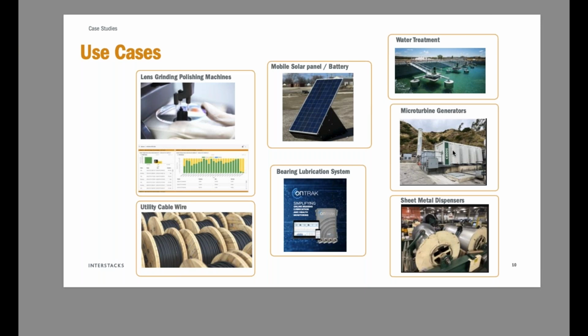We capture data from turbines and generators and send it to the visualization database. This company, Bearing Lubrication System, is an OEM that makes ultrasonic sensors for bearing wear and lubricating bearings, which is a big failure mode. We capture data from their sensors, package it up, and put it on dashboards. Alerts are generated if the sensor indicates bearing wear or soon-to-be bearing failure, so it gets lubricated.